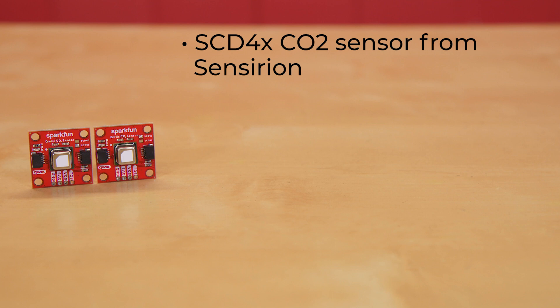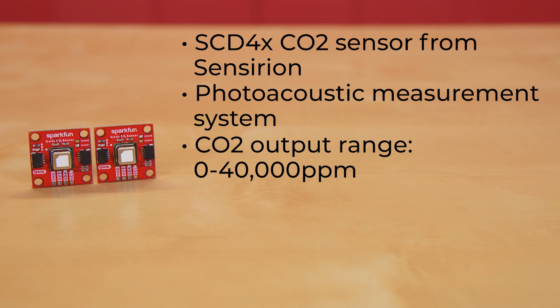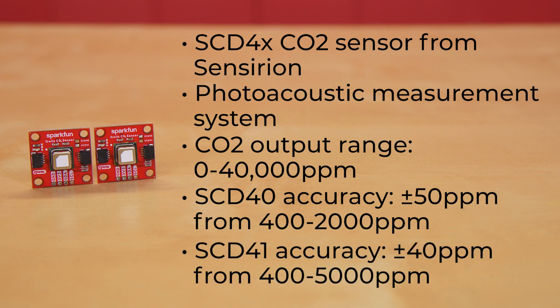These sensors use Sensirion's PASens technology to create a photoacoustic measurement system. They offer a CO2 output range from 0 to 40,000 ppm. The SCD40 will do that with a measurement accuracy of plus or minus 50 ppm in conditions from 400 to 2,000 ppm, while the SCD41 has a measurement accuracy of plus or minus 40 ppm in conditions from 400 to 5,000 ppm.